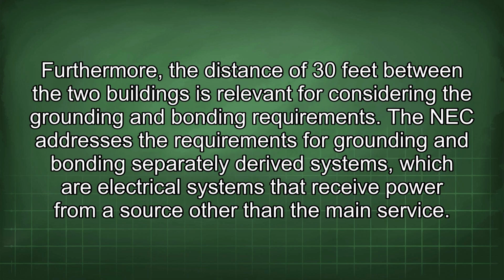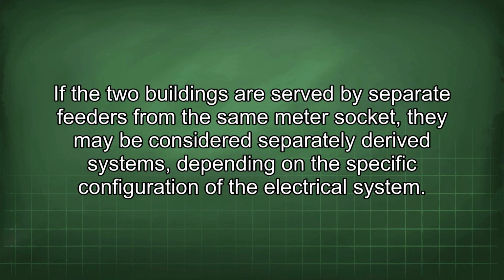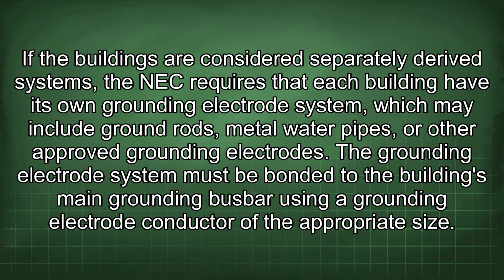Furthermore, the distance of 30 feet between the two buildings is relevant for considering the grounding and bonding requirements. The NEC addresses the requirements for grounding and bonding separately derived systems, which are electrical systems that receive power from a source other than the main service. If the two buildings are served by separate feeders from the same meter socket, they may be considered separately derived systems, depending on the specific configuration of the electrical system. If the buildings are considered separately derived systems, the NEC requires that each building have its own grounding electrode system, which may include ground rods, metal water pipes, or other approved grounding electrodes.